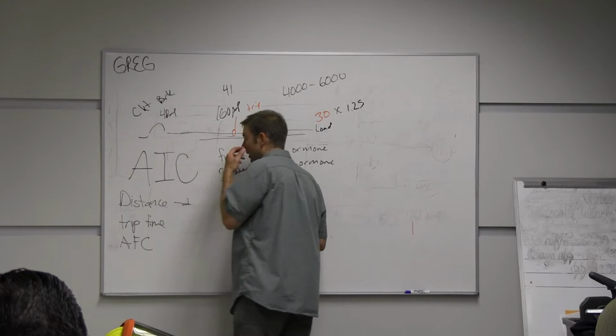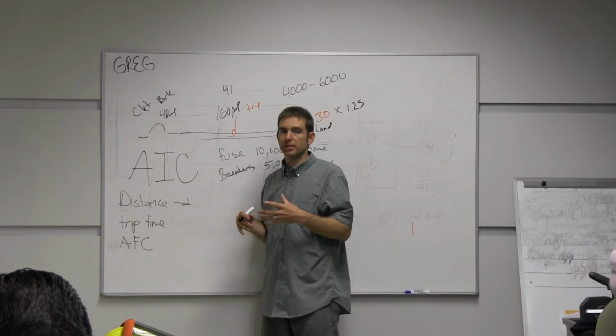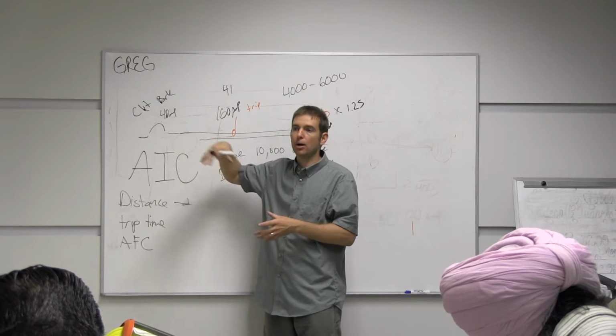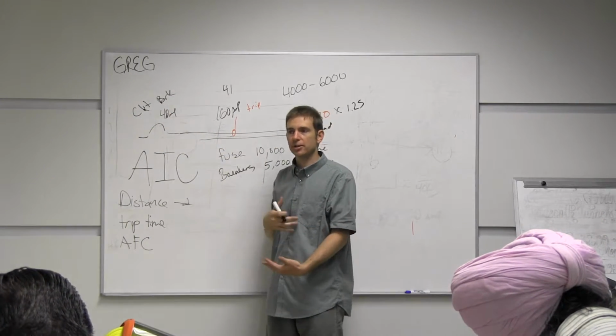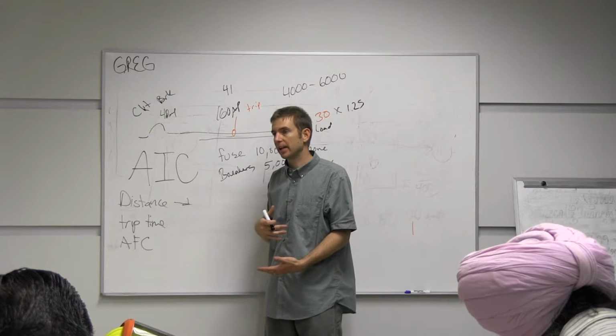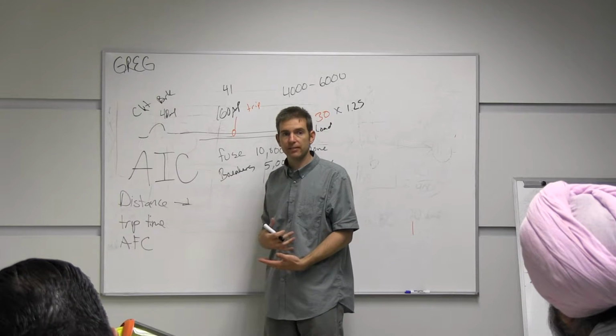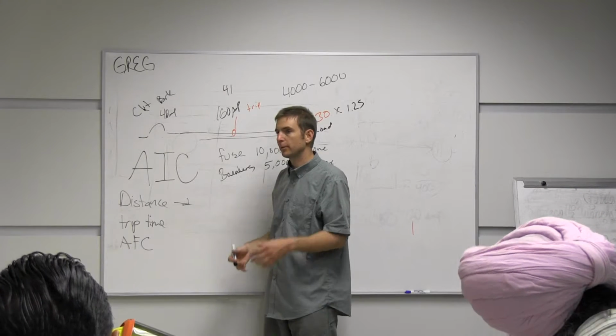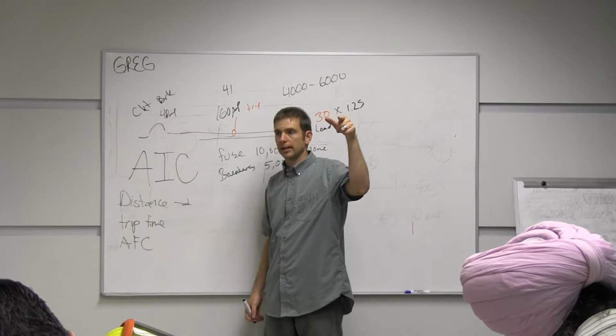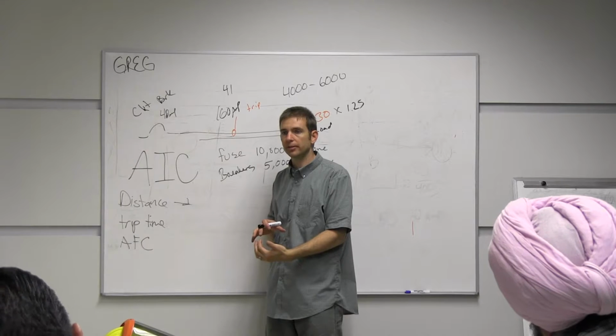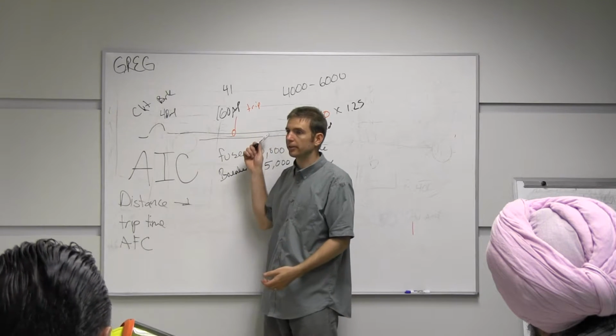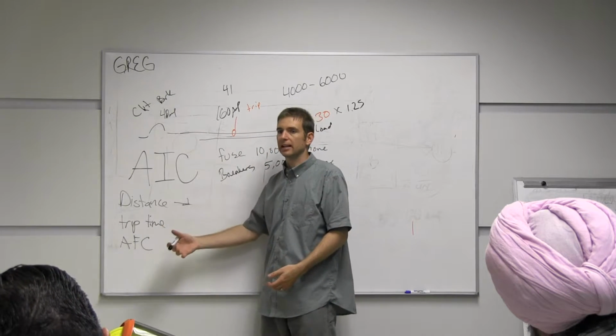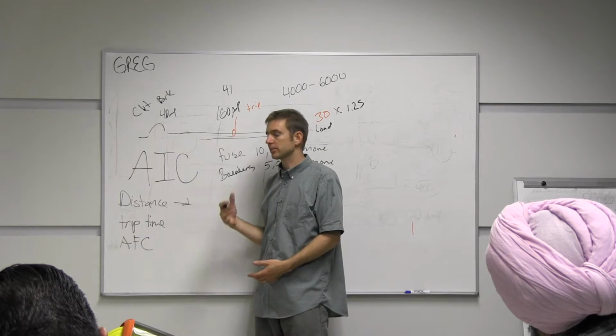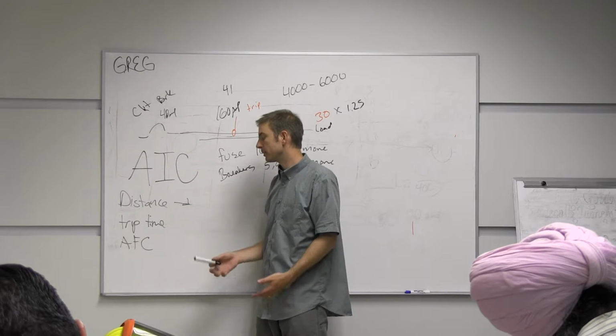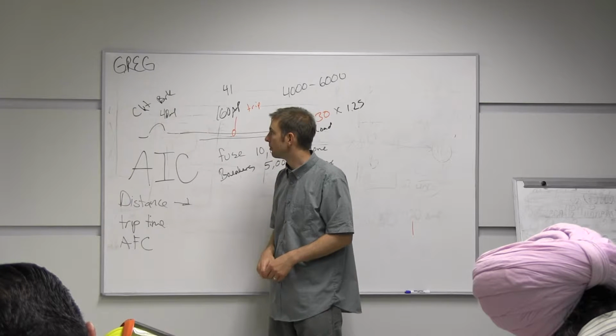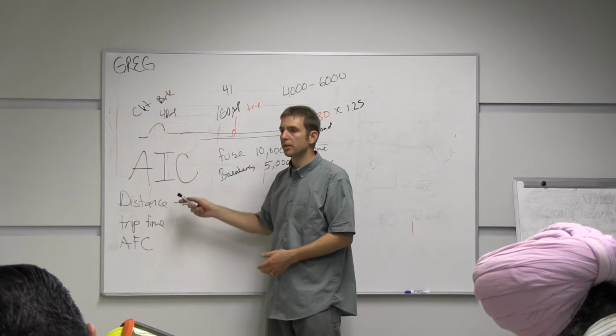So the utility company has transformers, and how far their transmission line, how big their transformer is. Is it a 150 kVA transformer? Is it a 15 kVA? I mean, how big is the transformer that they have? How big is the transformer that you guys have? The smaller it is, the smaller your available fault current is going to be, because it's only going to be able to allow so much fault current to pass through that transformer. So those are 3 things. There's probably a bit more than that, but these are the 3 big ones.